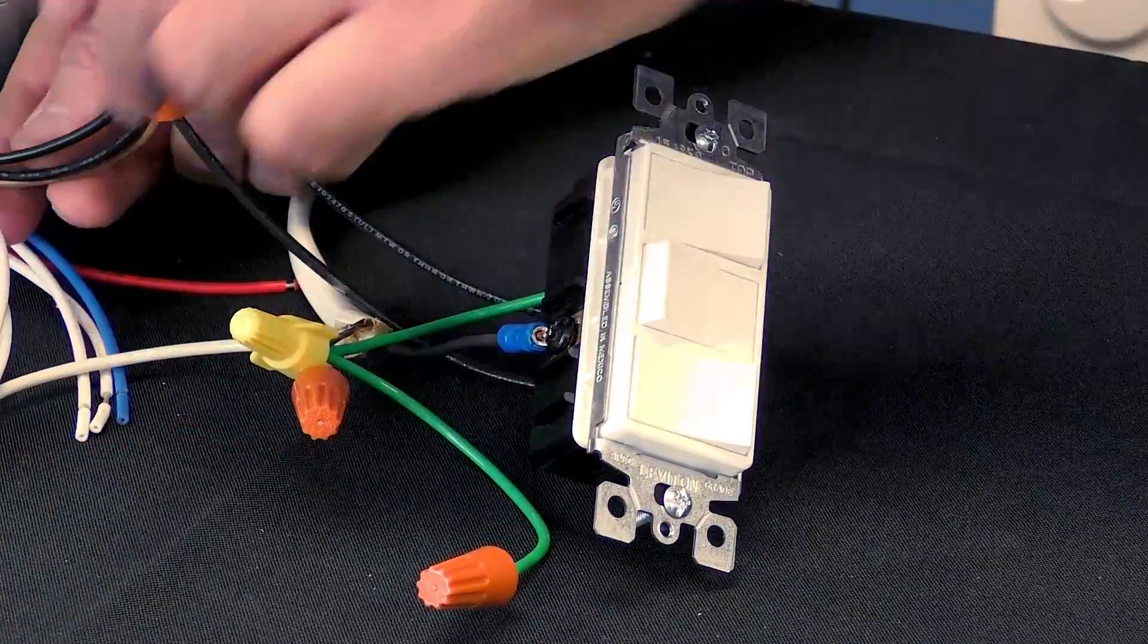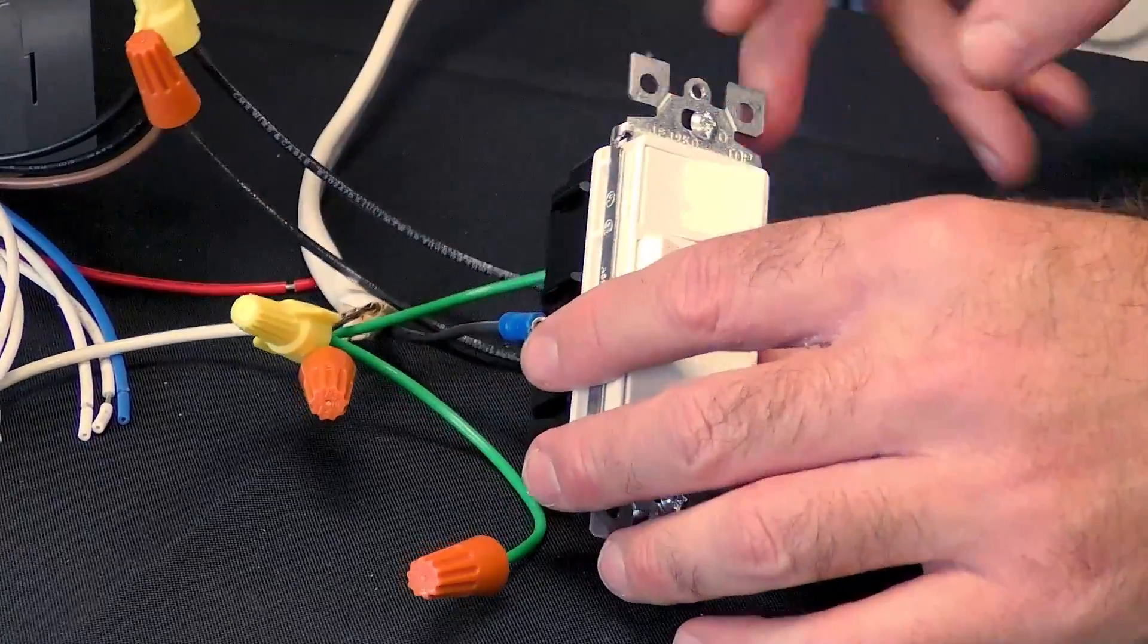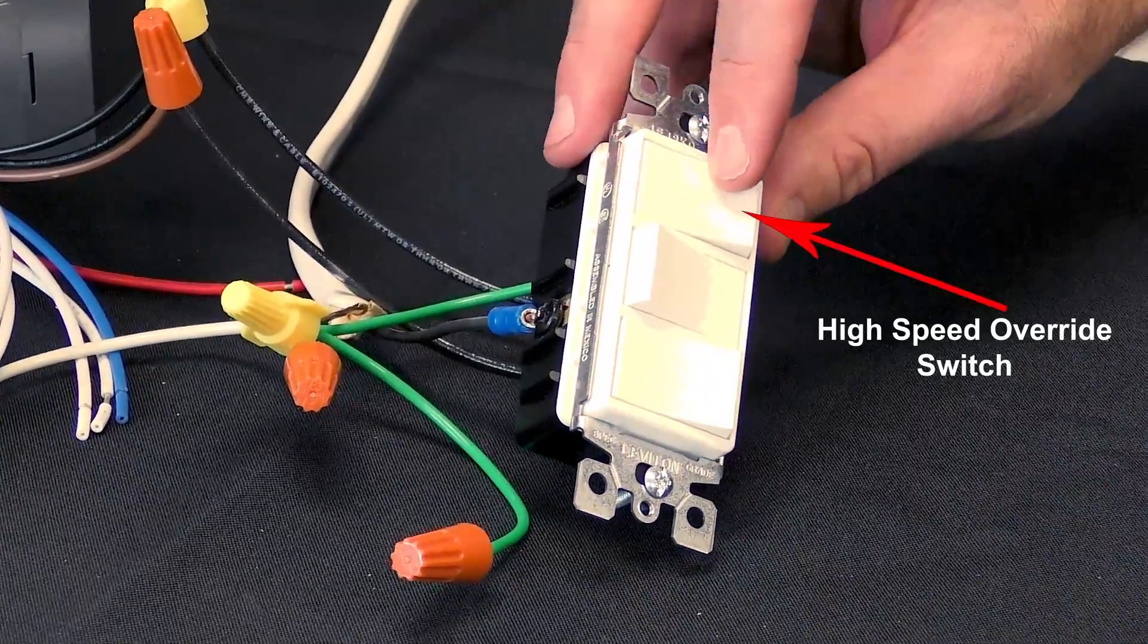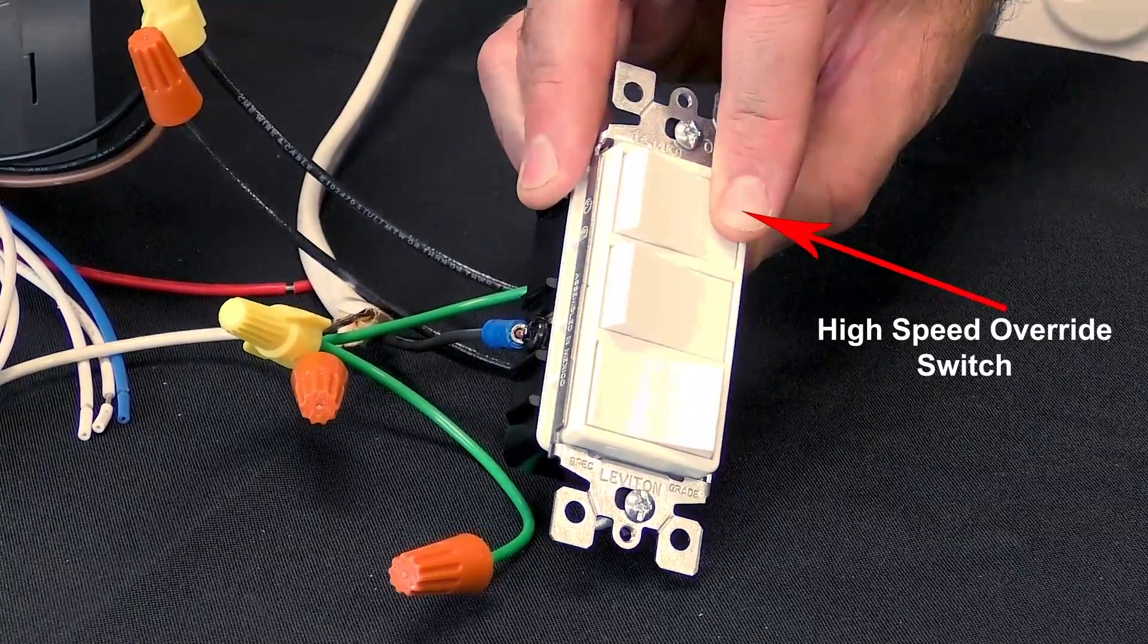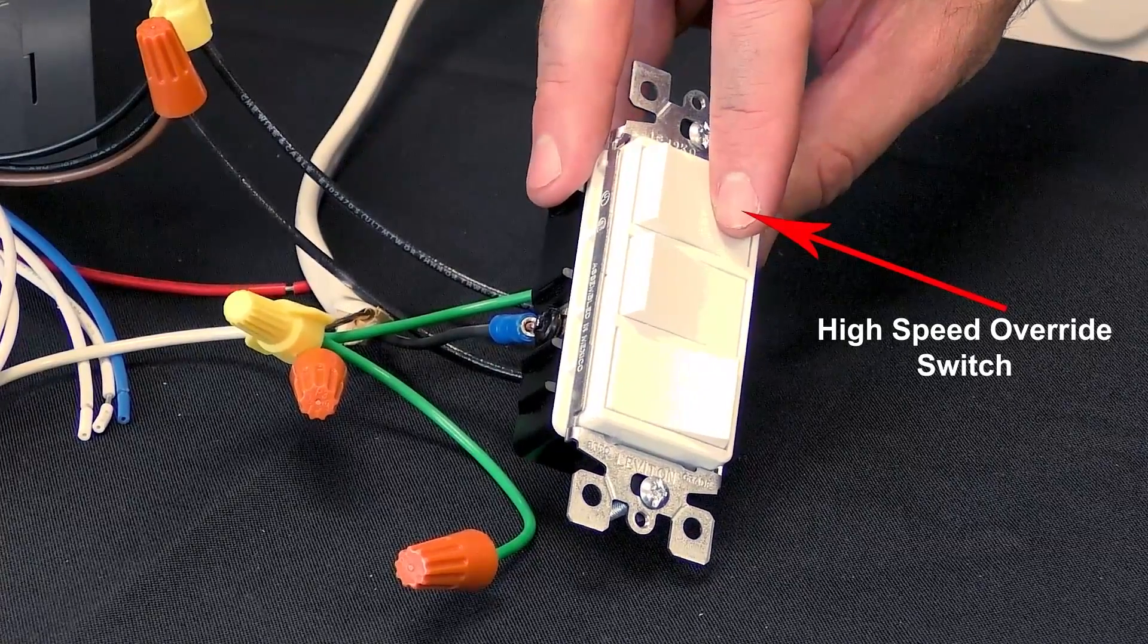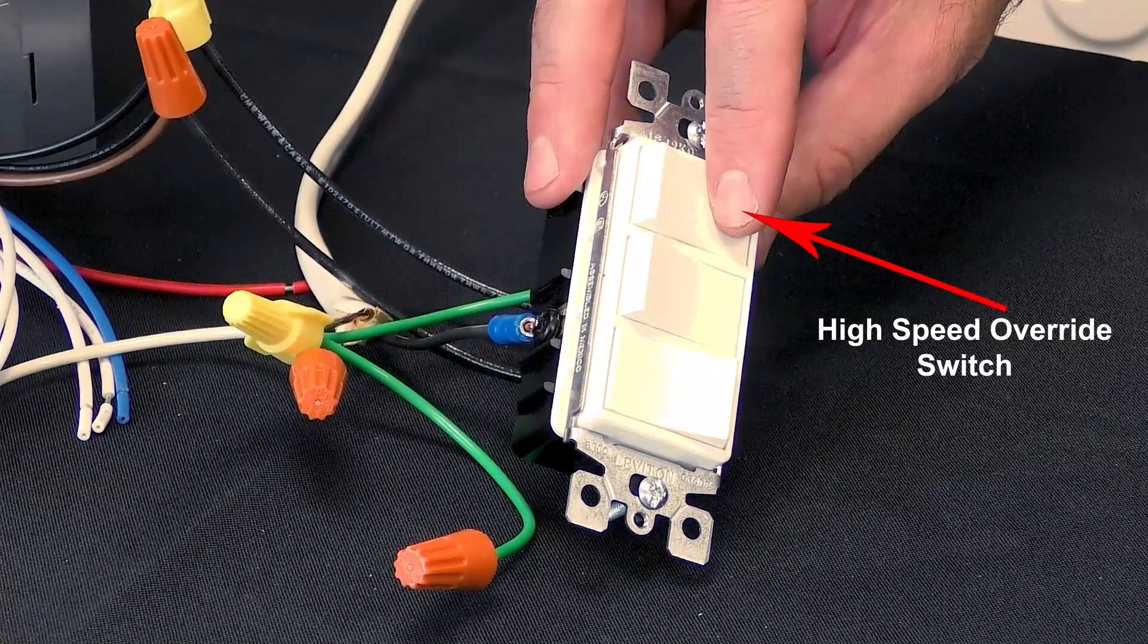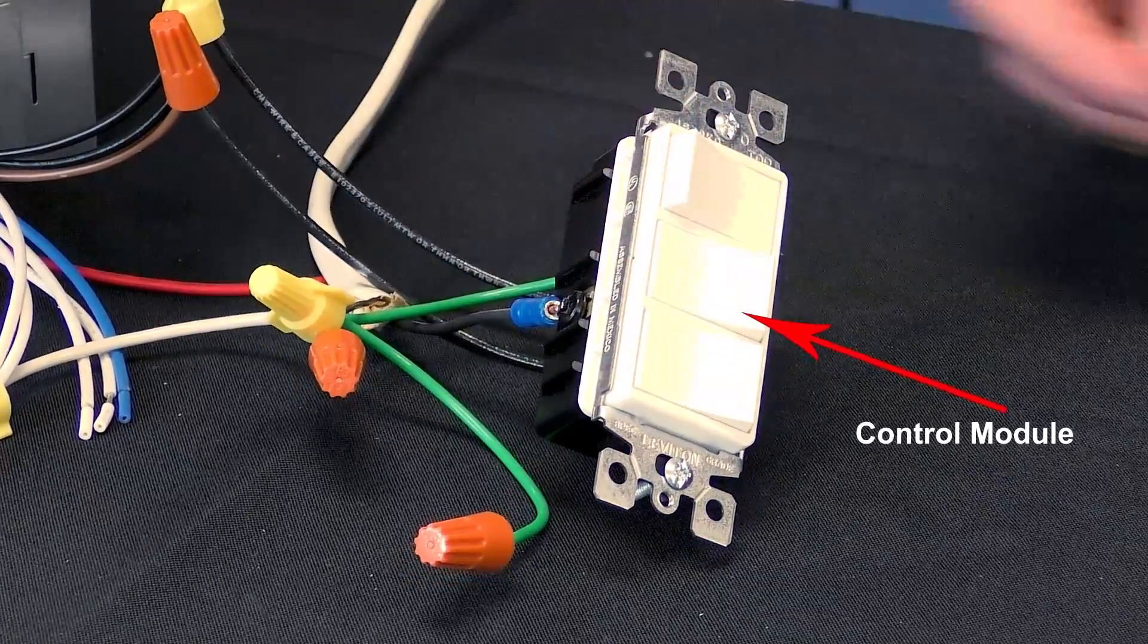The motor wiring harness and the associated switch is sometimes referred to as the high speed override switch, which overrides the control module operation to manually run the fan motor on high speed. It also runs the fan on high speed when the control module is switched to off.